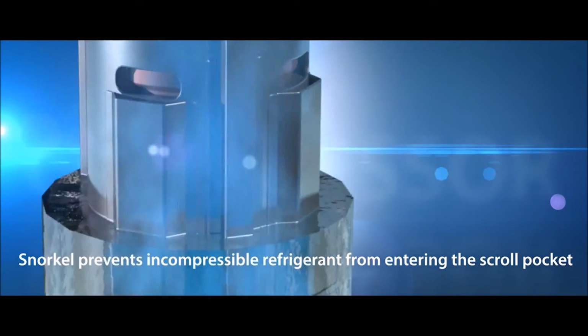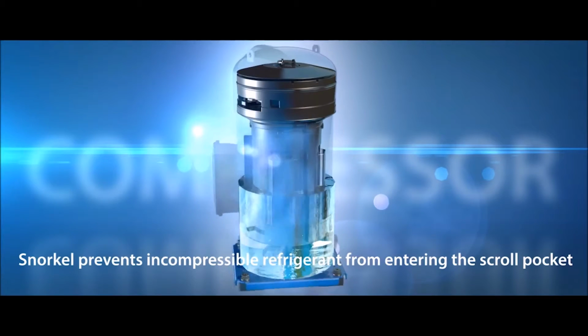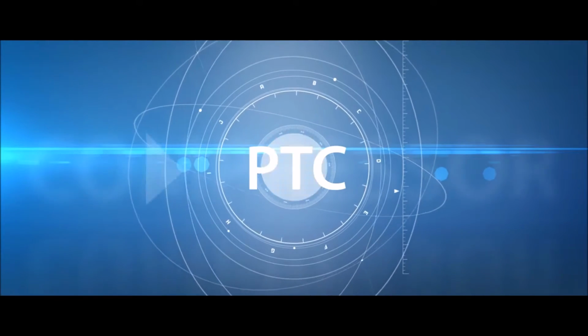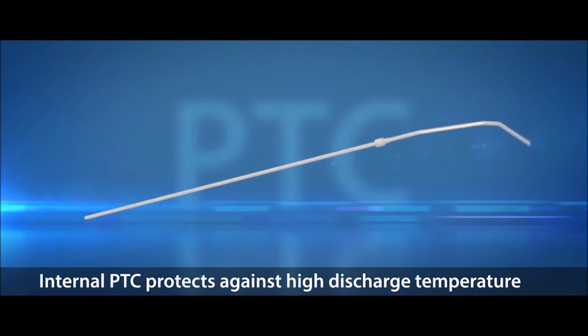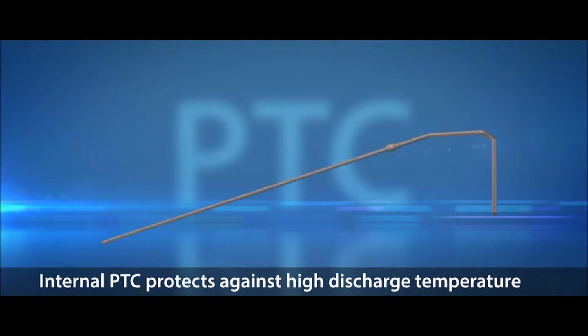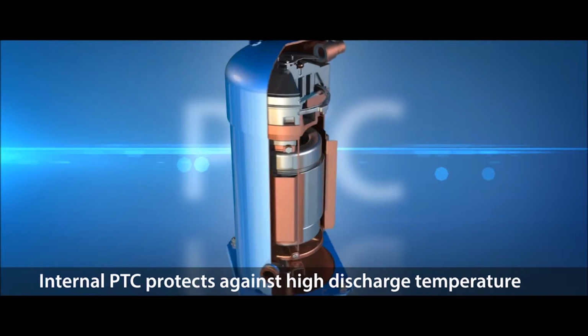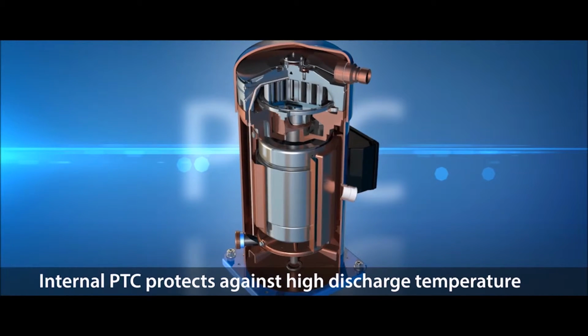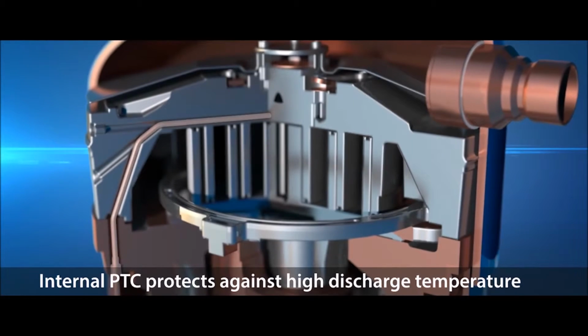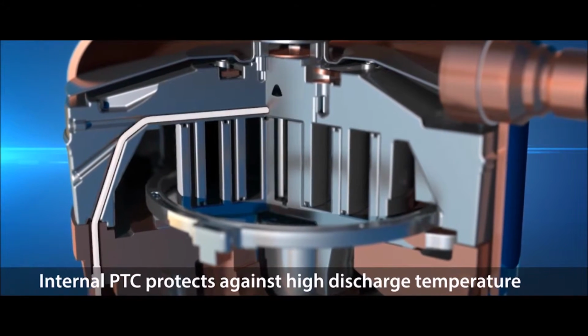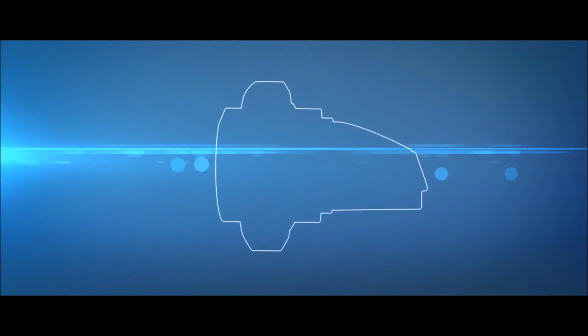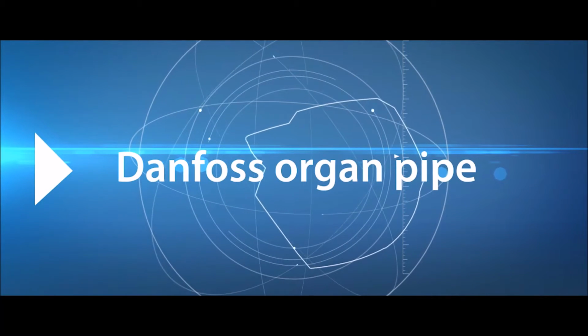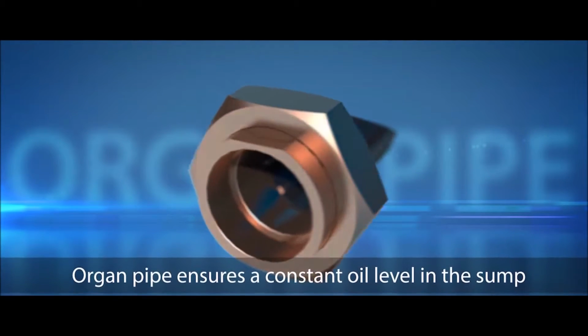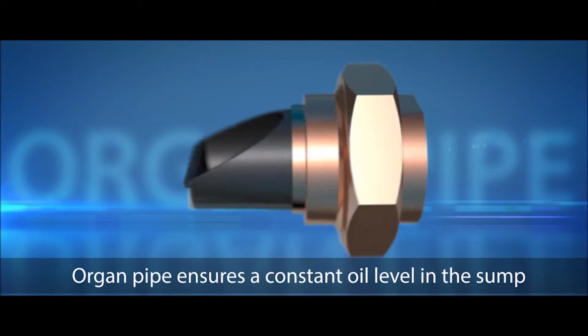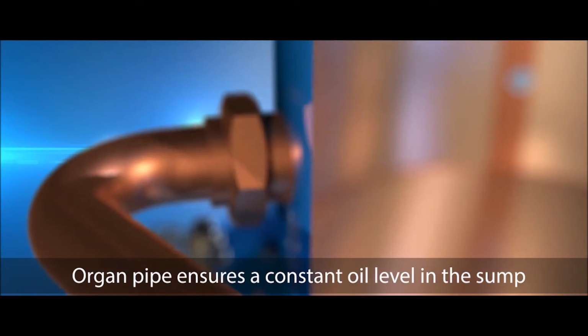The DSH is equipped with a third feature, the Integrated Discharge Temperature PTC in the fixed scroll. The PTC provides regulation of the internal discharge temperature, improving reliability of the operating map management. The application in manifold configuration is taken into account with the organ pipe. It ensures a constant oil level in the oil compressor sump, even when the system runs at part load. The organ pipe also makes it safe to restart the compressor from idle mode.